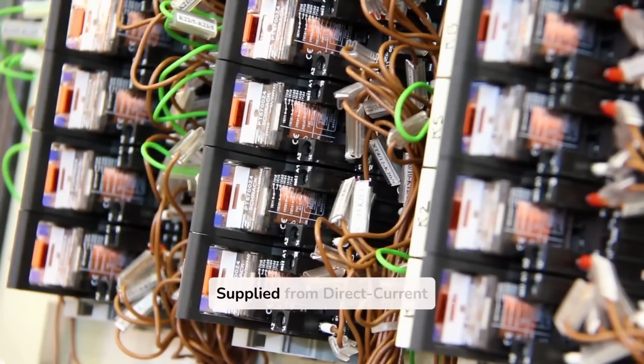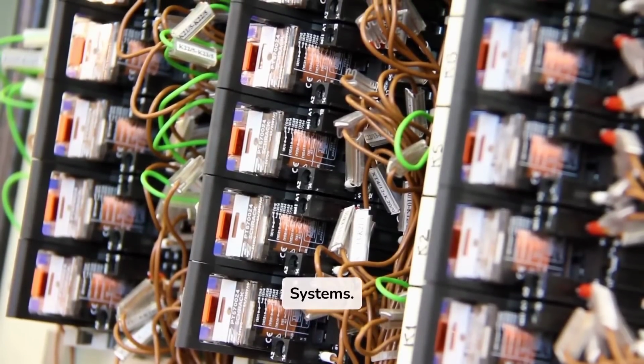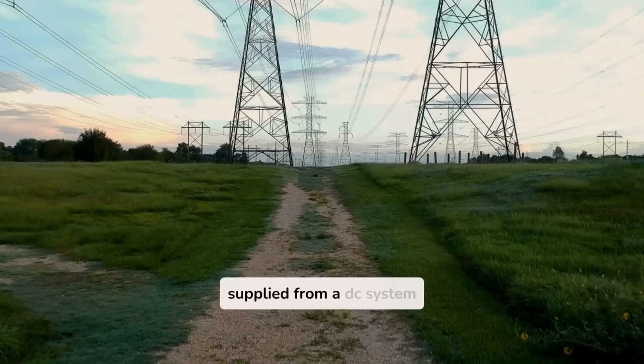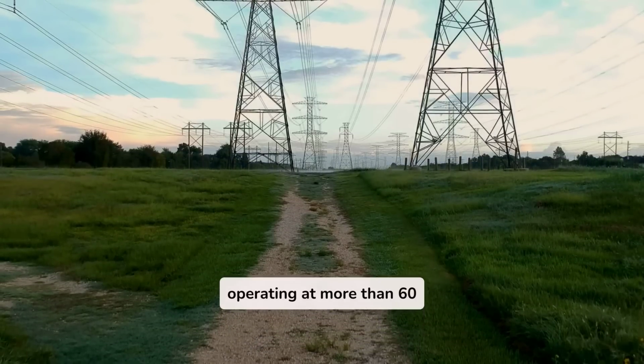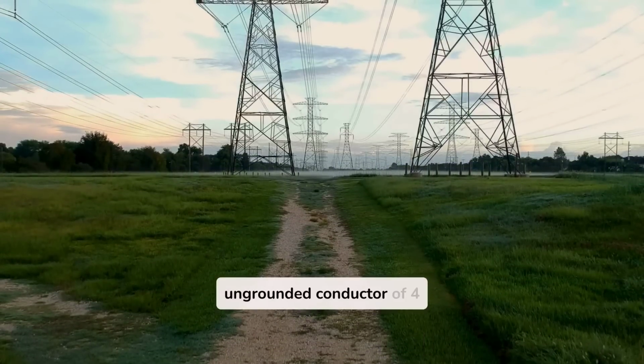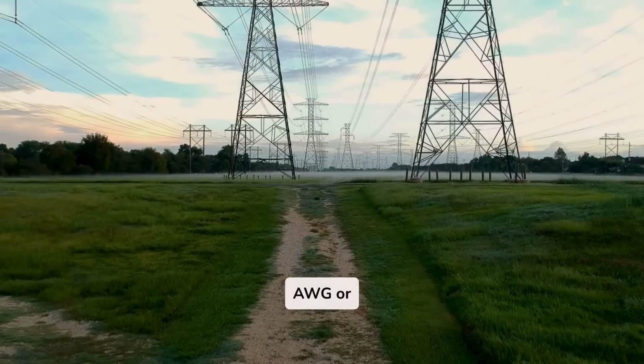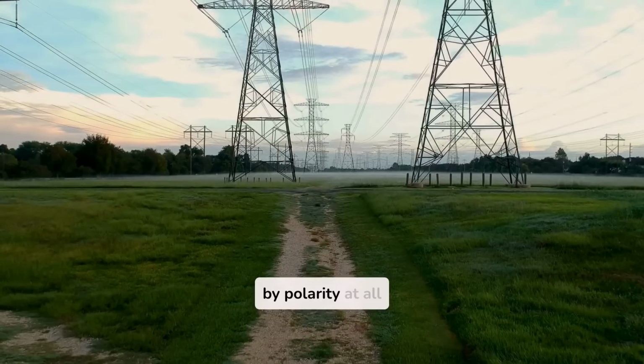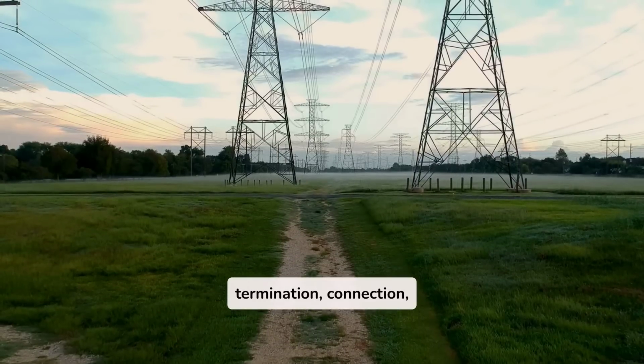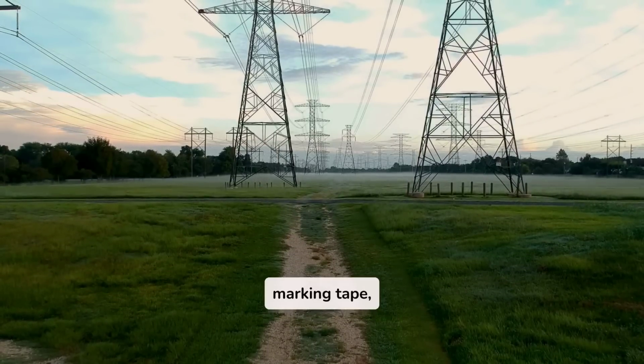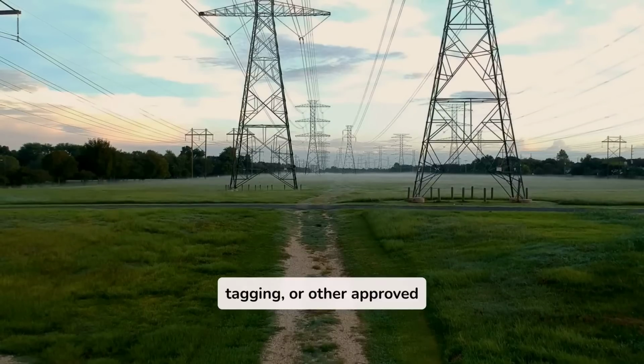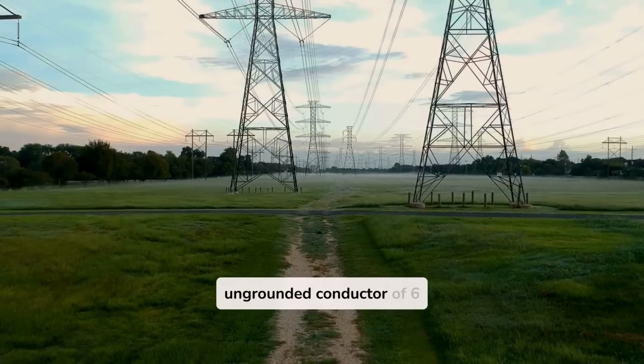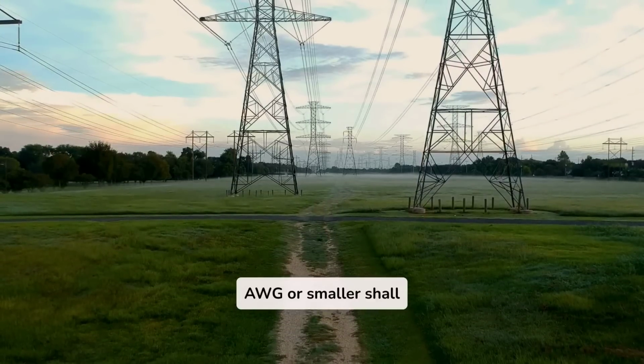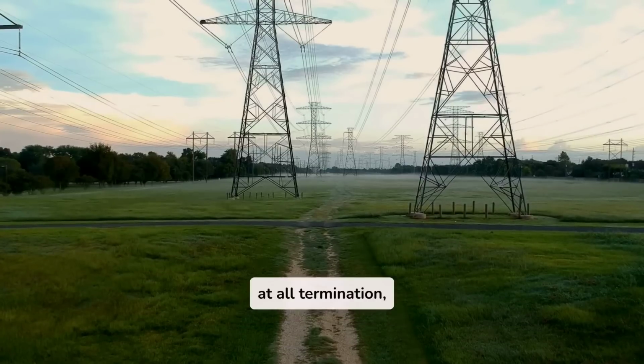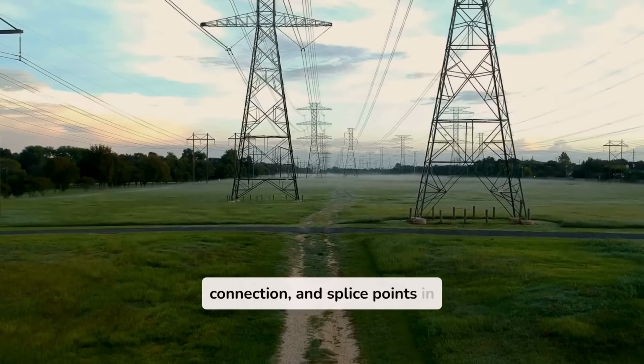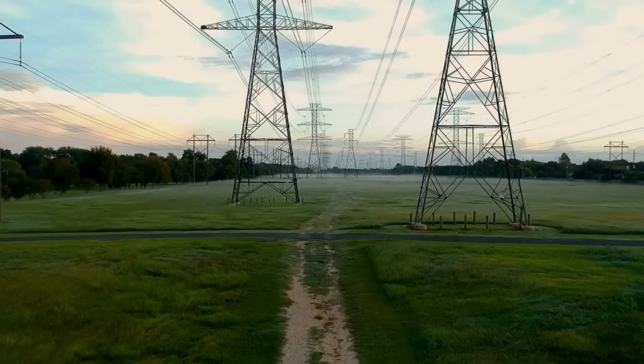2. Branch circuits supplied from direct current systems. Where a branch circuit is supplied from a DC system operating at more than 60 volts, each ungrounded conductor of 4 AWG or larger shall be identified by polarity at all termination, connection, and splice points by marking tape, tagging, or other approved means. Each ungrounded conductor of 6 AWG or smaller shall be identified by polarity at all termination, connection, and splice points in compliance with 210.5(C)(2)(a) and (b).